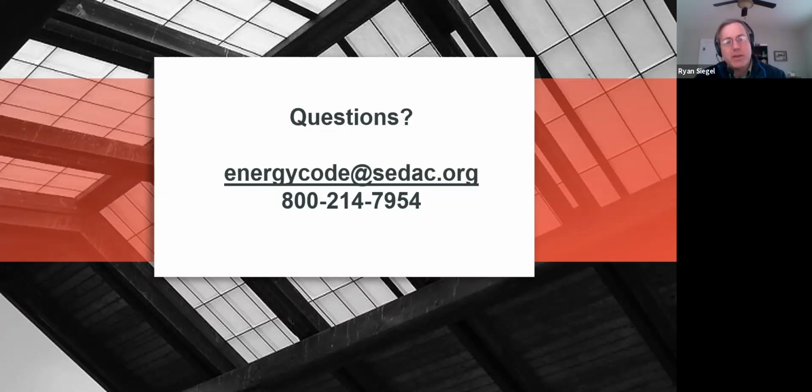Now what this kind of goes back to is the difference between a manual J and a manual S. So manual J, even if you size it to the negative 4 degrees, that I think may be found in the ASHRAE tables, it may say negative 4 degrees. The difference between negative 4 and negative 10 will likely be accommodated by the system size selection. So your next size up will probably buy you that buffer. And probably what you'll find is if you plug in negative 4 and then you go back and plug in negative 10, your sizing probably won't change between the two.